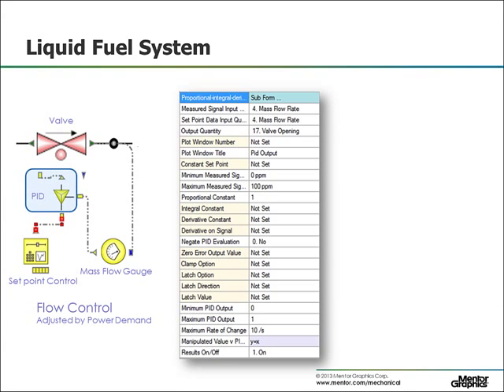To regulate the flow to our desired value requested by the set point controller, we use a mass flow gauge to read the current value of mass flow and feed that into the variable input of a PID controller to actuate the valve by the proper amount. You can see the data form for the PID controller here.